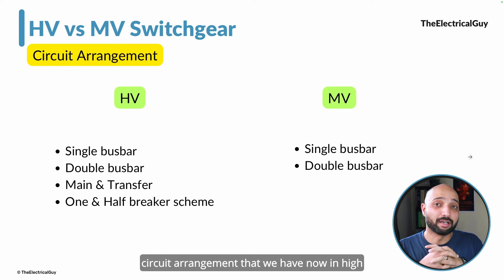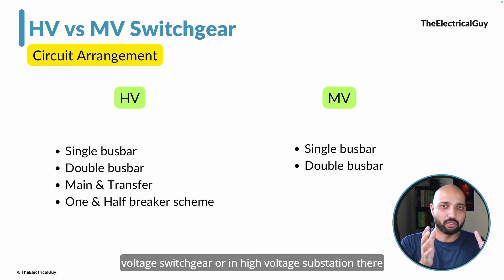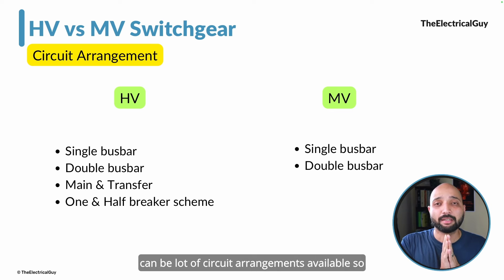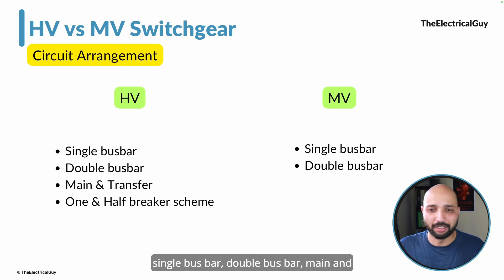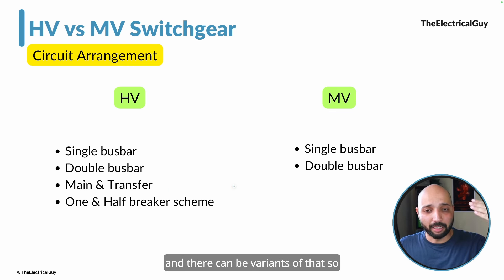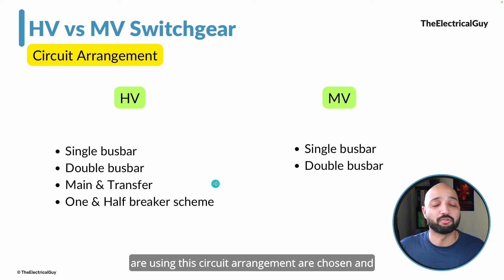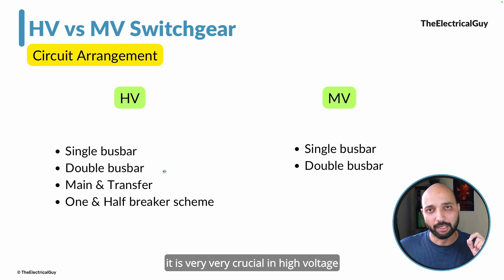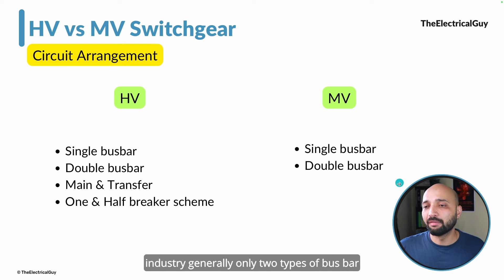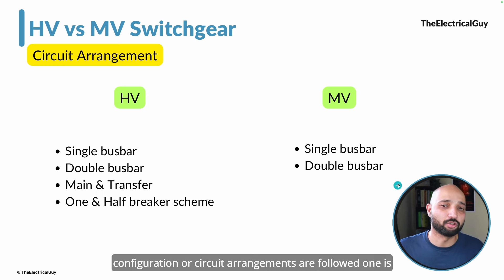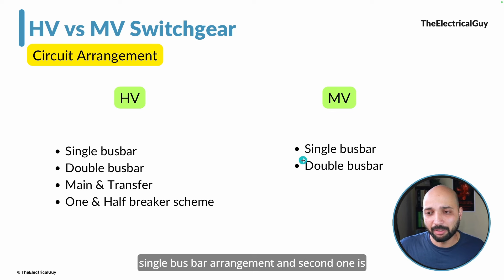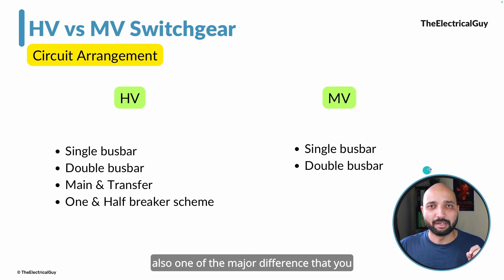Let's talk about the different circuit arrangements. In high voltage substations there can be many circuit arrangements: single busbar, double busbar, main and transfer busbar, one-and-a-half breaker scheme, and variants of those. These are very crucial in the high voltage industry. But in medium voltage, generally only two types of busbar configurations are followed: single busbar arrangement and double busbar arrangement.